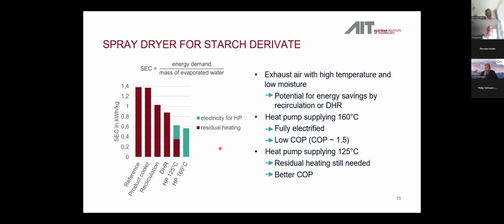By adding different heat recovery measures, we get different energy demands for this drying process. The reference without any heat recovery measures is nearly 1.4 for the specific energy consumption, which is the energy demand divided by the mass of evaporated water. This specific energy consumption gets better by adding the different heat recovery measures step by step. In this case, the exhaust air is at a very high temperature and low moisture, so there is some potential for recirculation and a large potential for direct heat recovery.